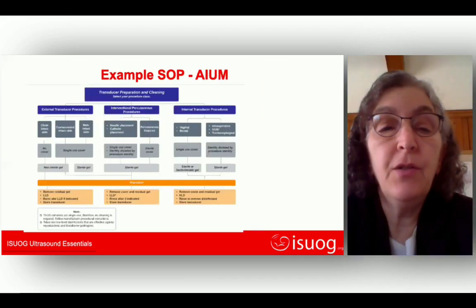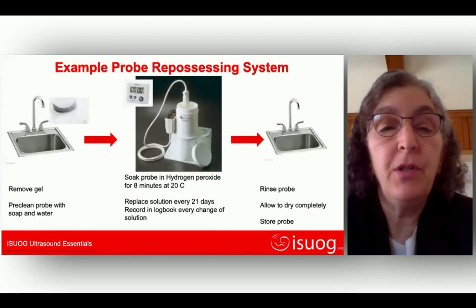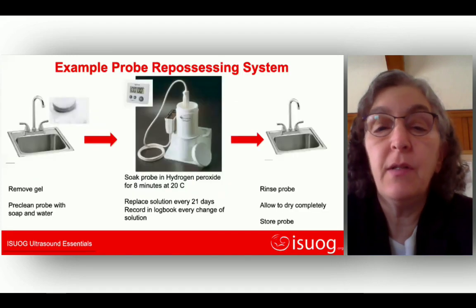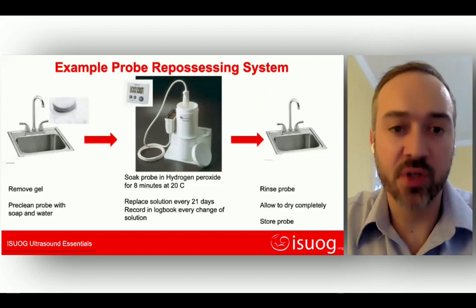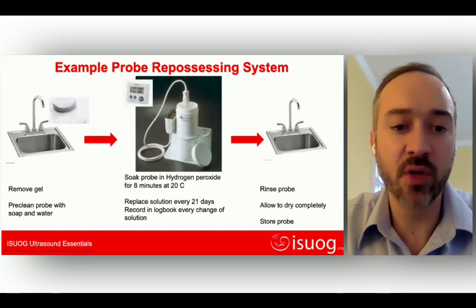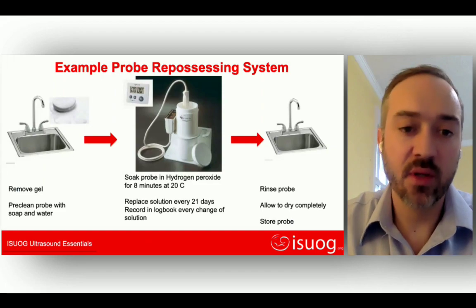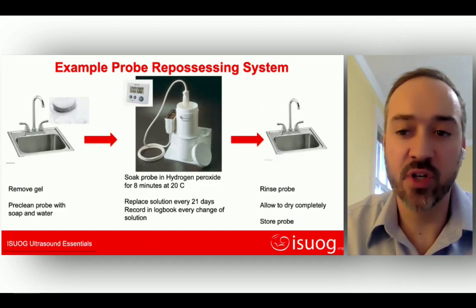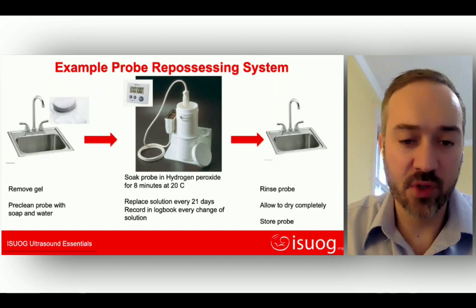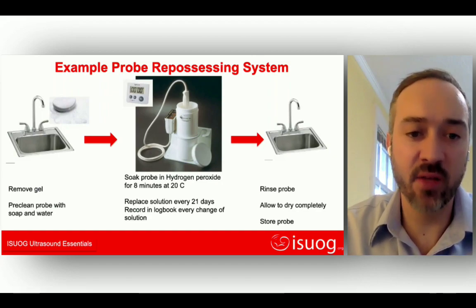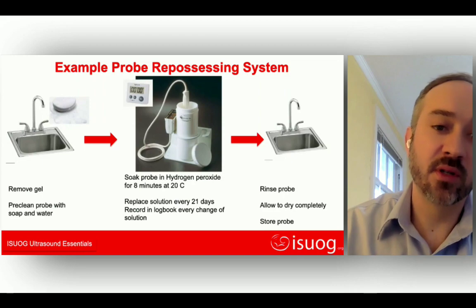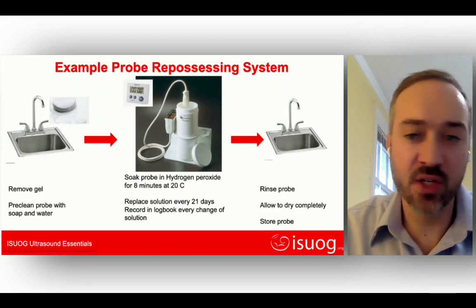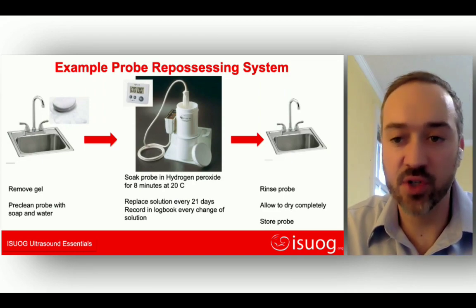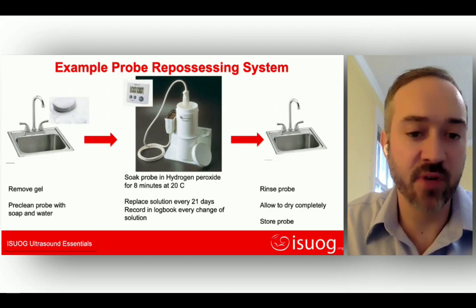So Ben, do the handles need to be cleaned as well when you're using these processing systems? And how about the cables? That is a very good question. So yes, the handles and the cables do need to be cleaned, but they can undergo a low-level disinfectant. The part that actually goes in the body needs a high-level disinfectant, but anything else that you just touch with intact skin can be cleaned with a low-level disinfectant, just a standard disinfectant wipe.